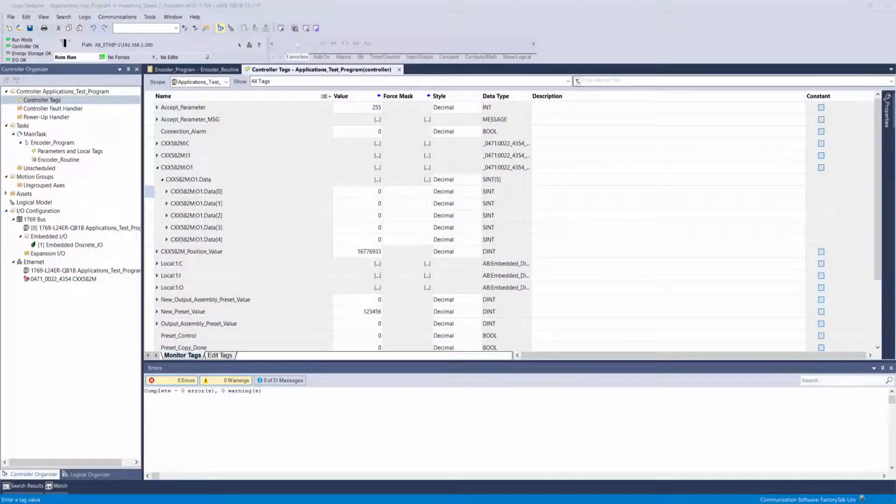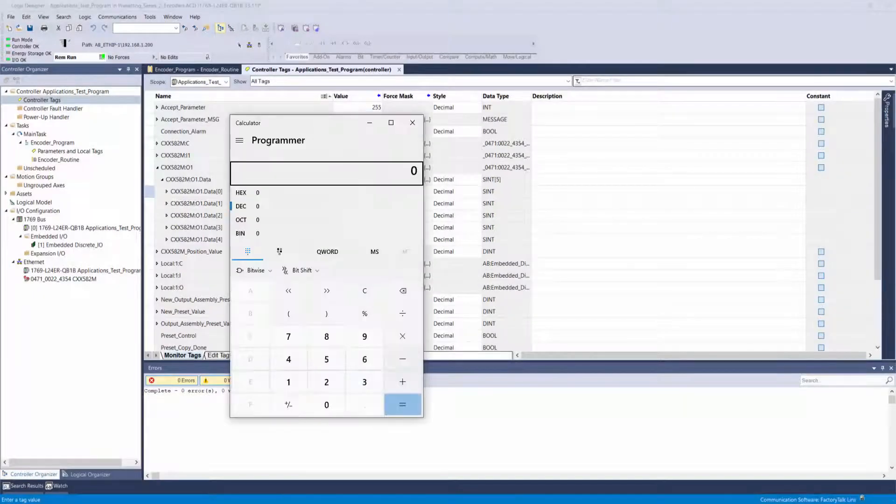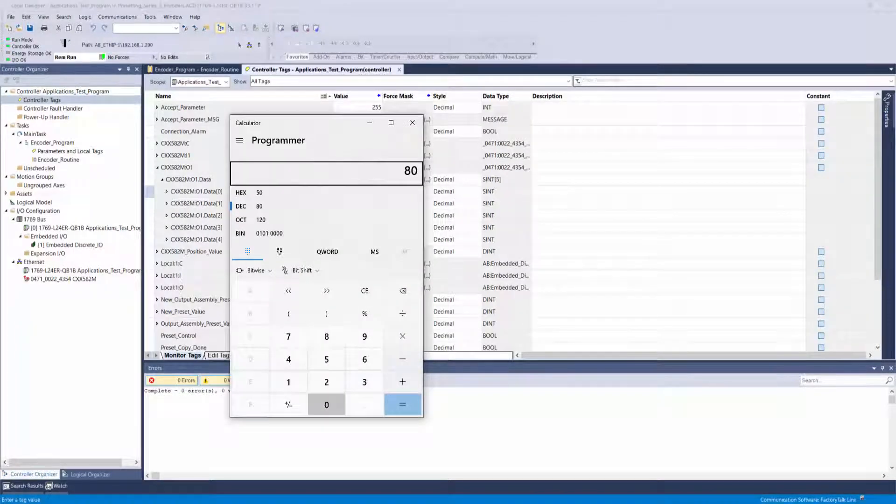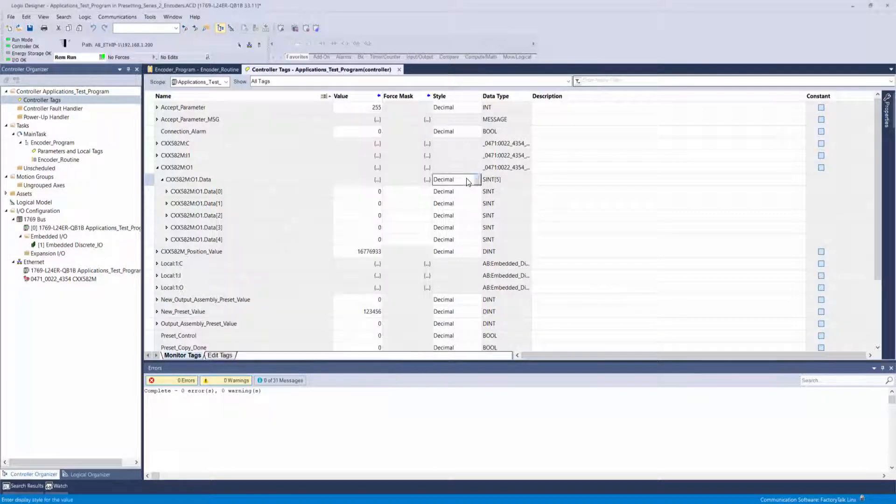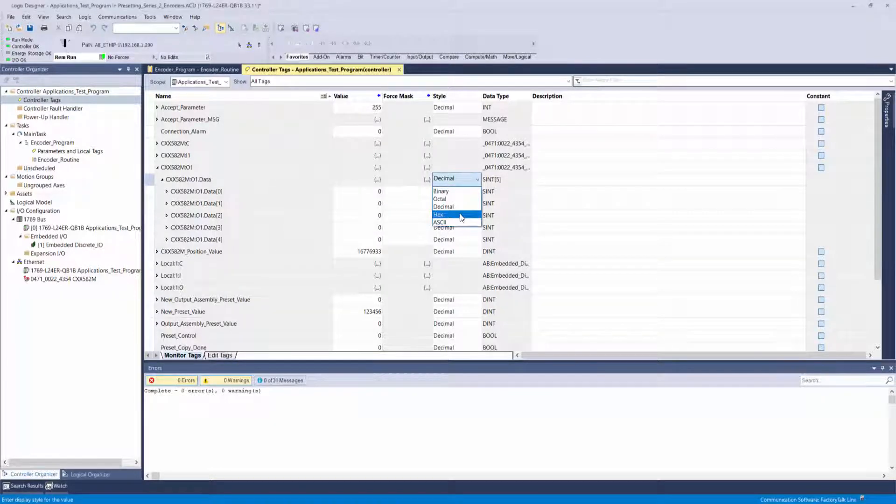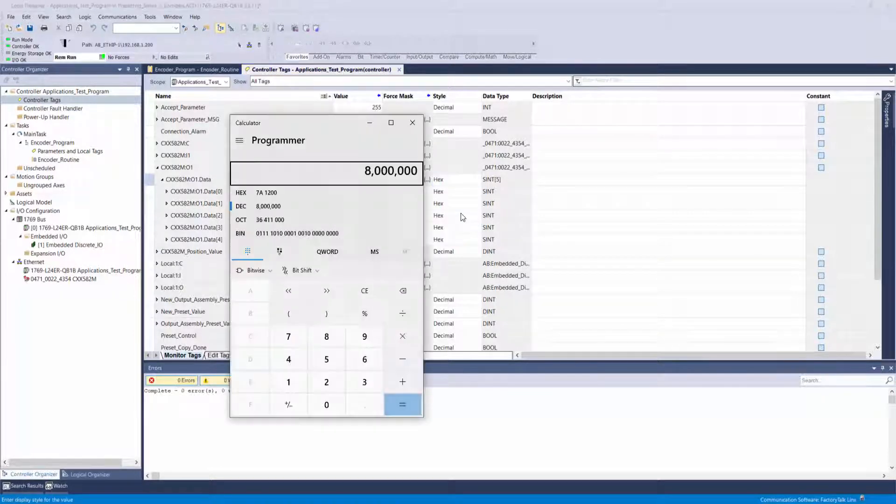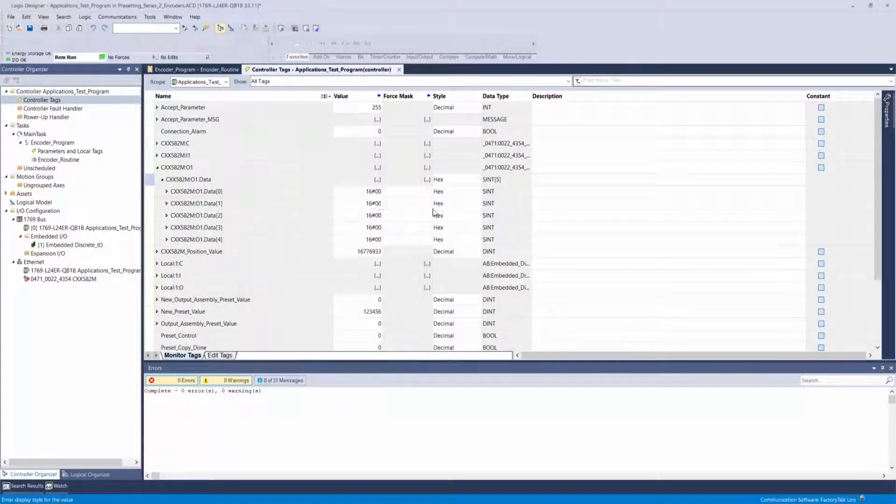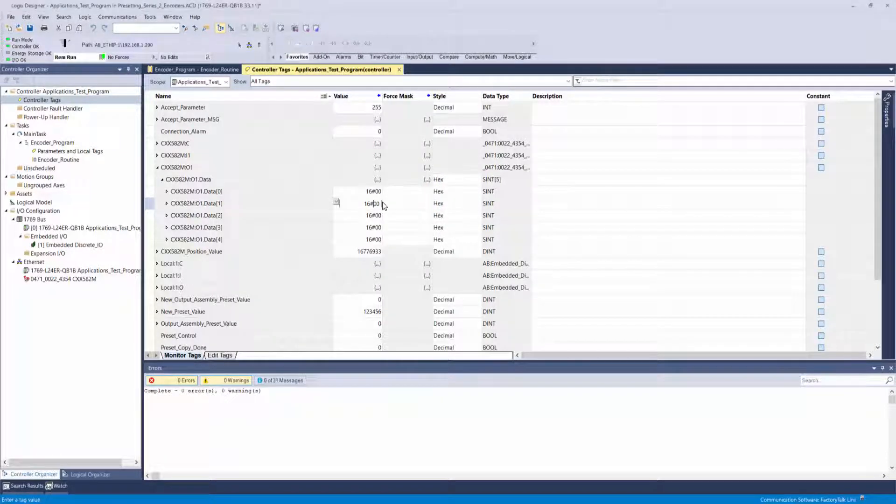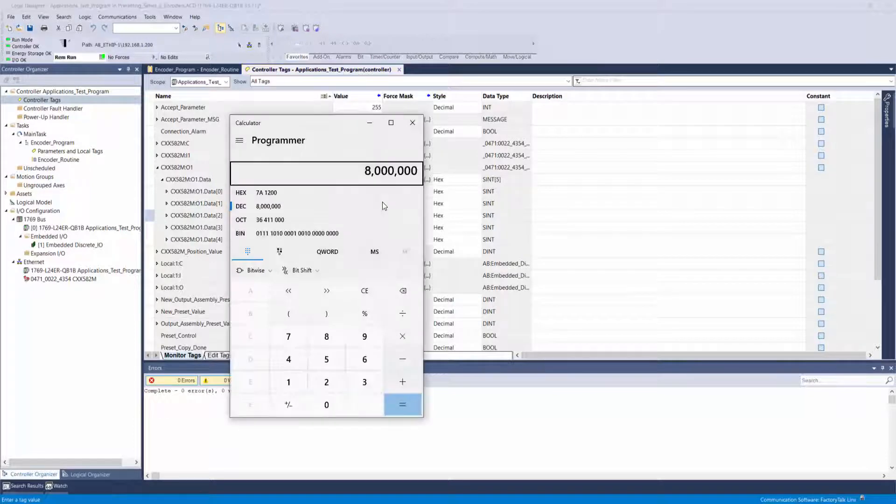Alternatively, you can use your programmer's calculator to convert your desired position value to hexadecimal, then simply enter the value two digits per output assembly tag, beginning with your least significant byte 0 and working your way down to the most significant byte 3.